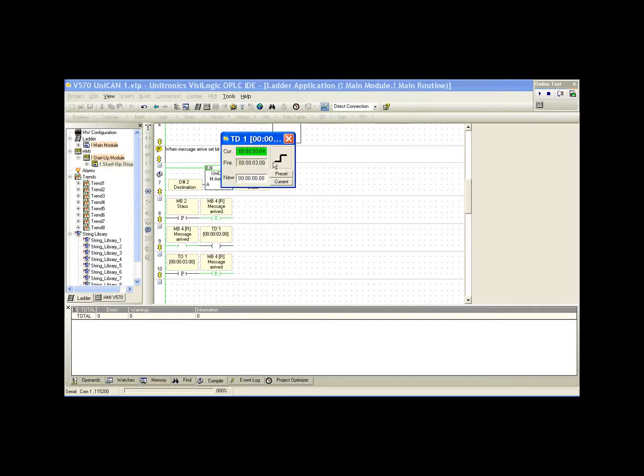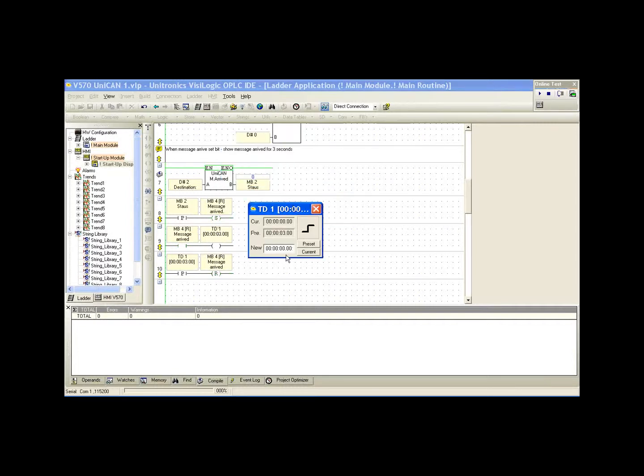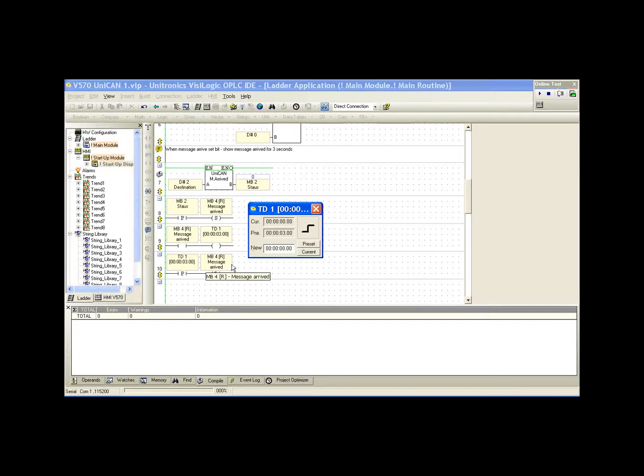We notice what it's doing is activating a three-second timer. After three seconds, it resets itself. This is a message arrived binary text message we have on the HMI. Whenever we receive a message from ID 2, MB 4 will be set. MB 4 is a display variable. So we'll display the message arrived. With our timer 1, after three seconds, we're going to reset the message. It's a simple way to notify us that we've received a message. In a real situation, we can use this information. The message arrives and we can either copy the information to the appropriate registers or we can perform some function. These are the tools available. It's up to the user to decide how they want to use them.